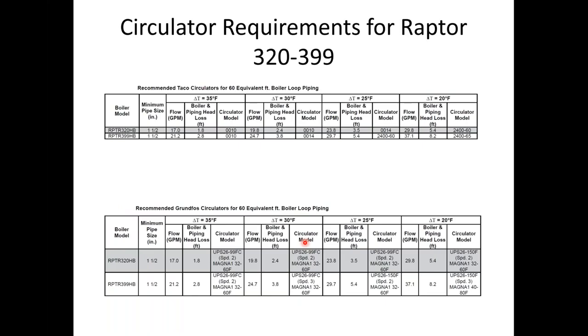The larger boilers, the Raptor 320 and 399, are going to require a little bit of a larger pump. They're moving more BTUs out of them. Again, the pumps that are listed here are for the near boiler piping. If they're going to be direct connected, we would need to size accordingly for both the boiler and the system. I talk a lot in my Hydronics 101 training about running a 30-degree delta T on condensing products. That's basically where we want to see these things live the majority of the time, with that 30-degree delta T, so we're able to get them to condense more. So 0010 or 0014 will be absolutely fine for the 320 and 399, or the Grundfos equivalents, the UPS 26-99; it'll be on speed 2 for the 320, and the UPS 26-99 for the 399 would be on speed 3. So one pump at different speeds will work for both of the boilers.